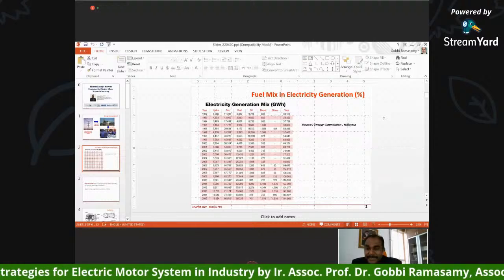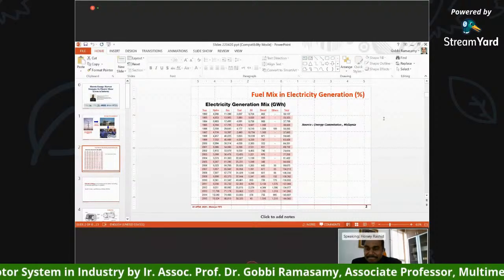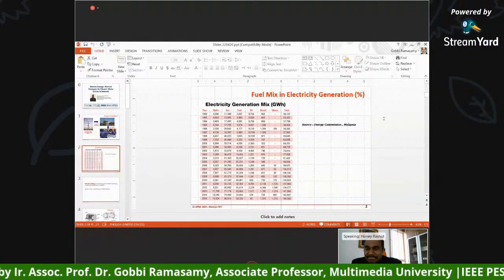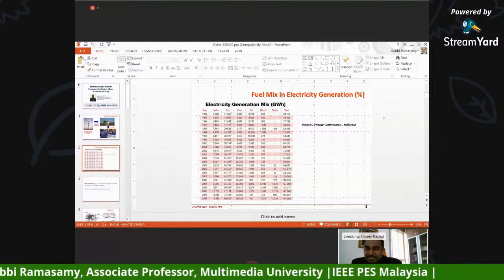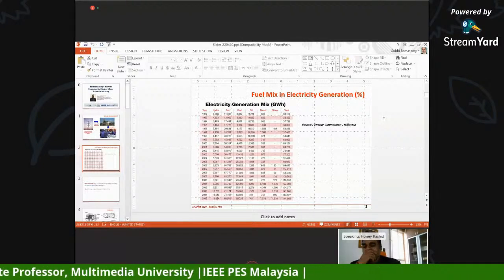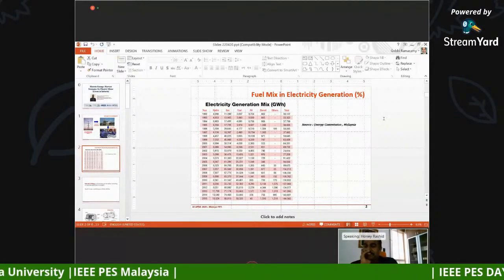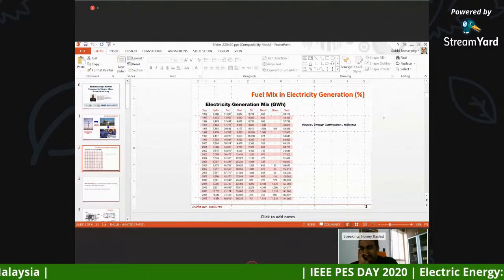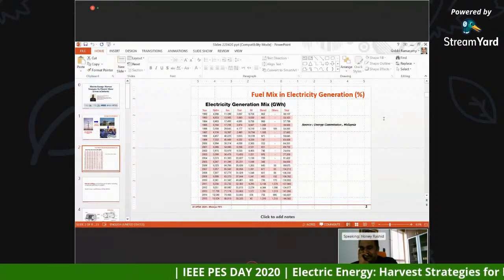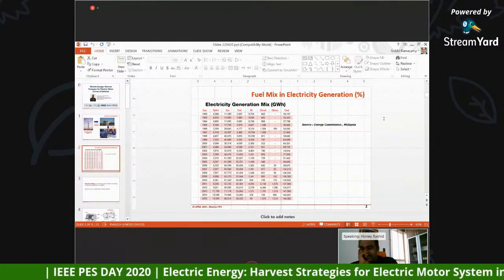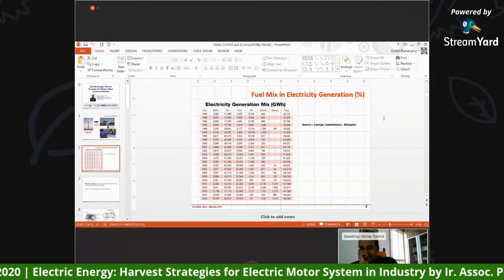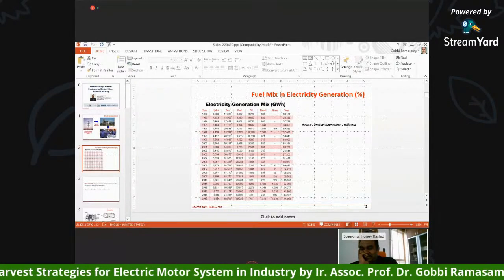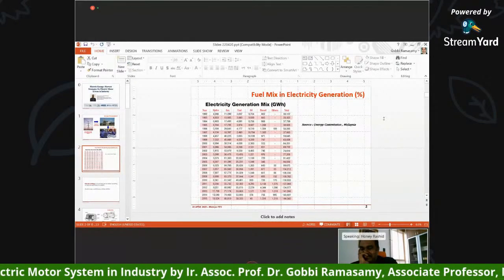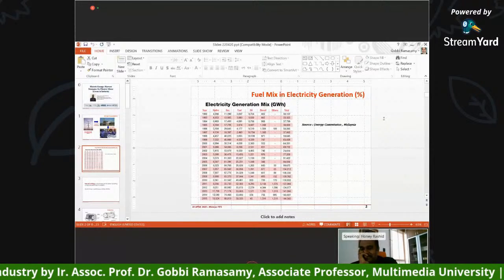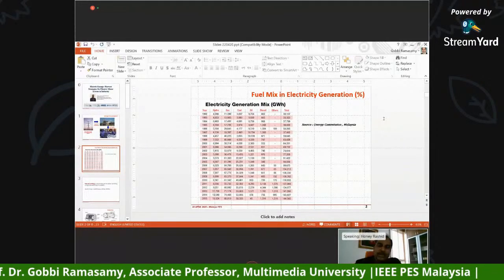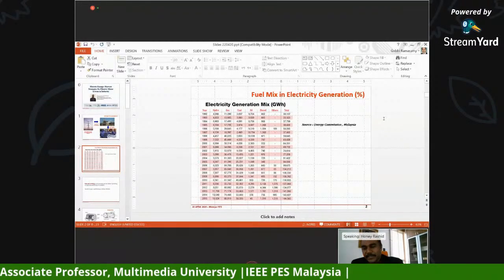There is another question from the same participant. On your slide number 6, he wrote that you said one of the ways to increase motor efficiency is to use large diameter copper. But isn't it that large diameter copper will create more loss due to skin effect? Don't we need to use a smaller diameter of copper wire but more quantities and in a standard configuration to have better efficiency? Yeah, it's a good question.